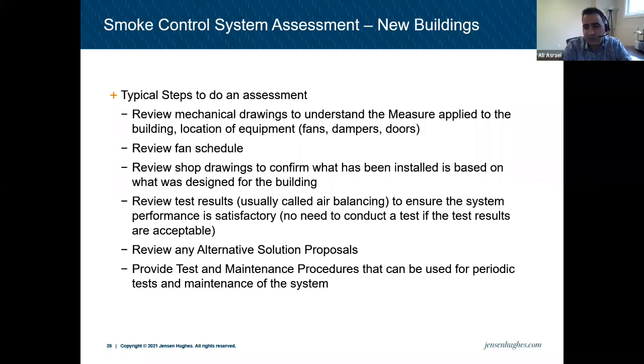The other thing is that, okay, the system was installed, but is it performing properly? This is a 10,000 CFM design, and a 10,000 CFM fan was installed. Is it performing as a 10,000 CFM or is it deficient? You don't know. Even if it's a new product, sometimes they're deficient. So this is where you need to ask for the test results. Usually they call it air balancing in the project. A lot of HVAC contractors call it air balancing results.